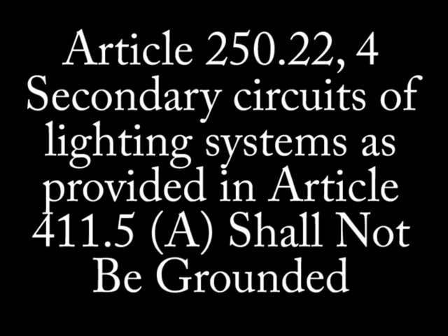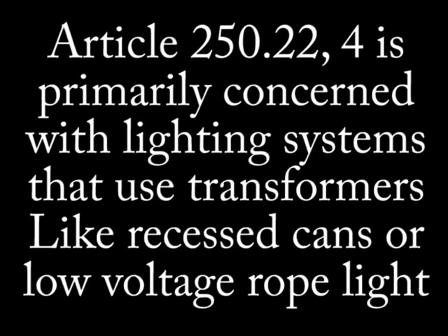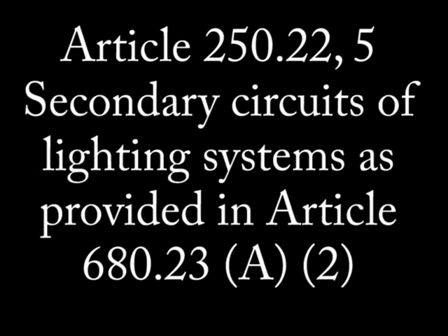Part 4: Secondary circuits of lighting systems as provided in Article 411.5 Section A shall not be grounded. This would apply to something like recessed cans that use a step-down transformer or a transformer-fed low-voltage rope lighting system.